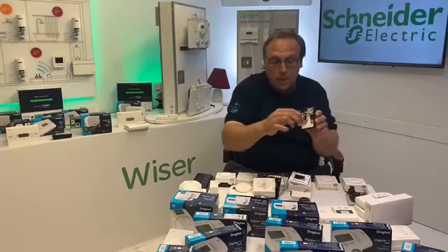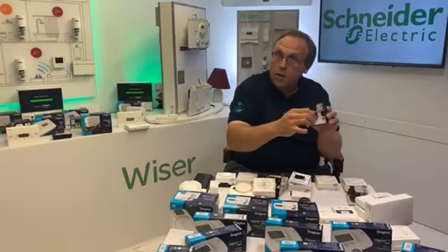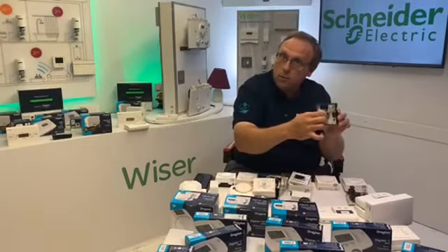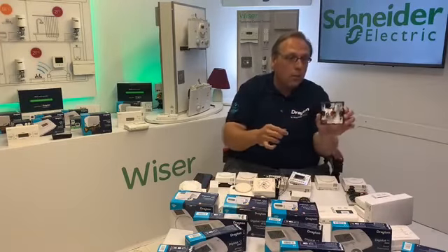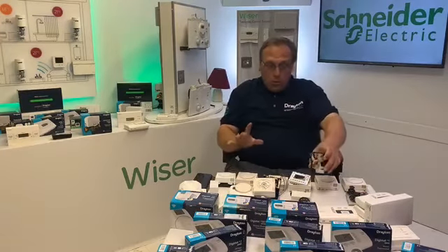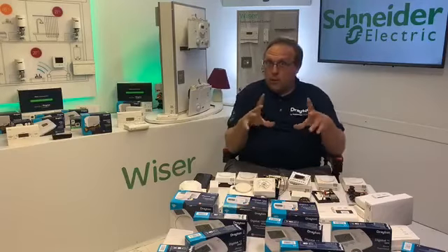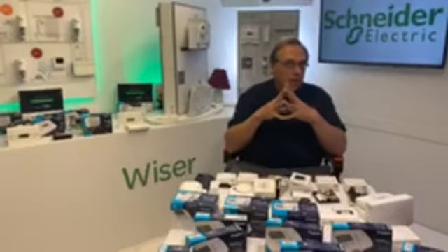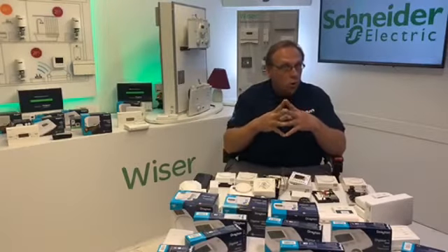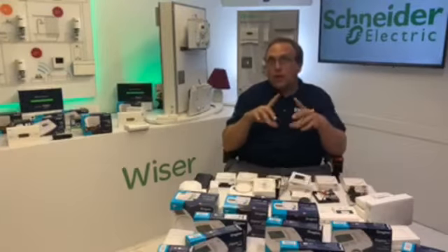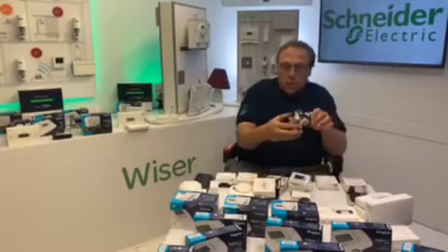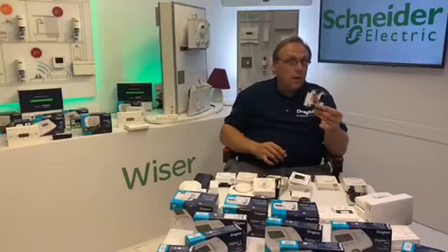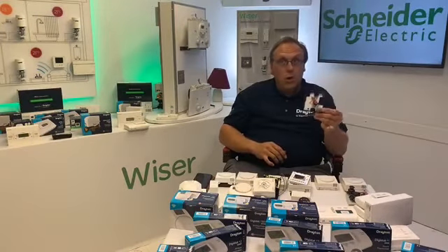Now this is a bimetal thermostat, so you do hear it click as you go past set point. And the reason it's called Combi is for combi boilers, and that's something that a lot of people get hung up on, because it's not for combi boilers. It's called Combi because there are multiple ways that you can wire it. So this is a really good thermostat to keep on the van, because whatever you come up against, you're going to be able to use it.